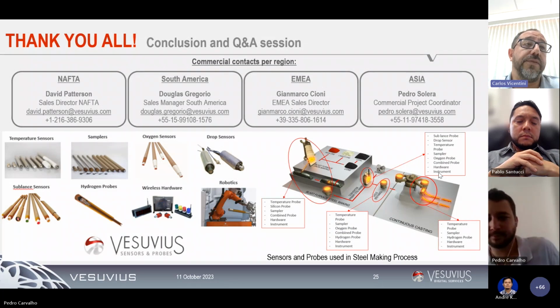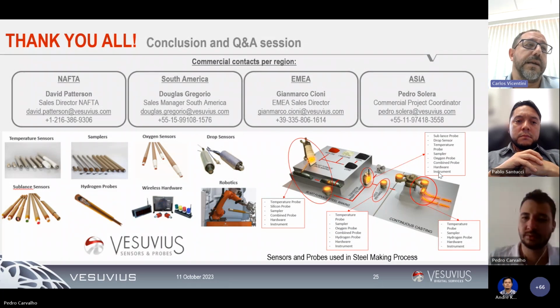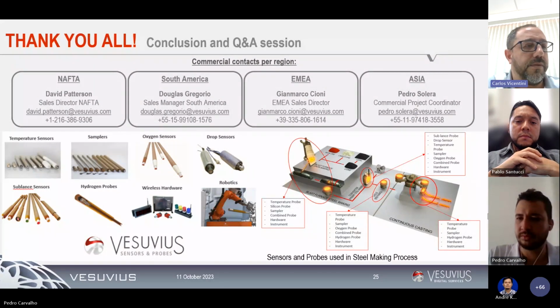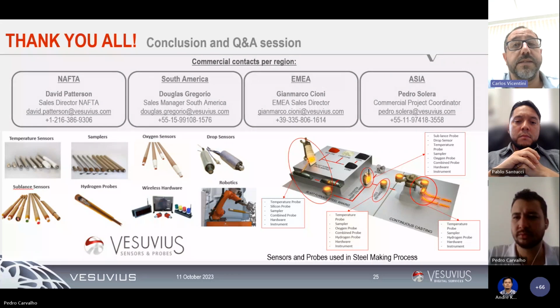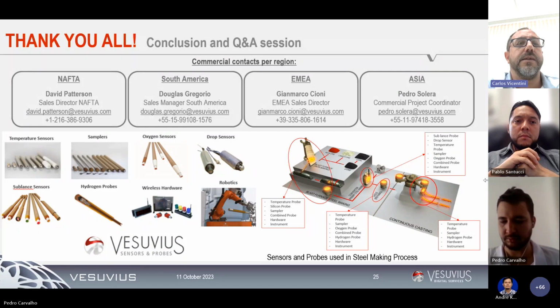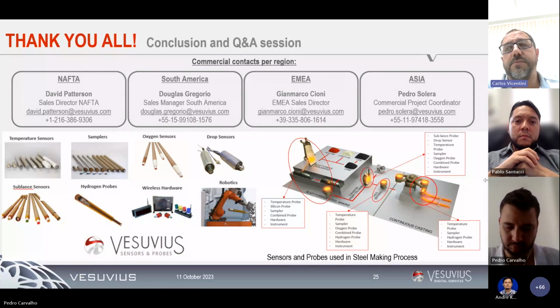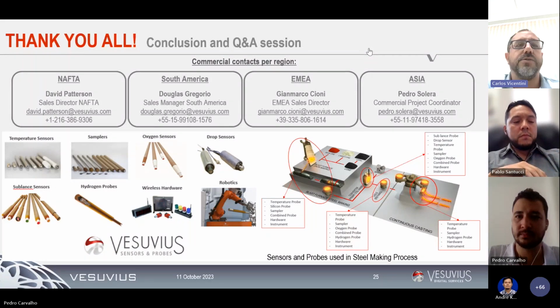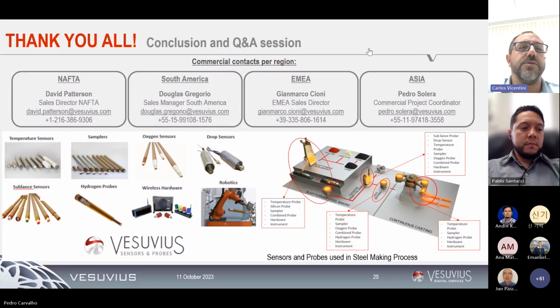And usually, if the steel mill has good tubes and a good line in terms of guaranteeing the purity, when they enter our system, no problem. But it's not easy to get this purity when you use the inline nitrogen. So we recommend using the bottle because it's more of a guarantee to keep the purity very high during the system measurement.